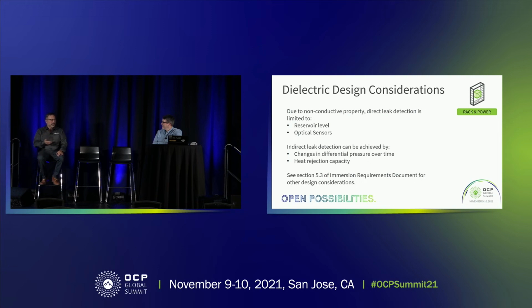Yep. Some of those ancillary things that you don't think about that leaks could cause. The first thing you're thinking about is, oh, I'm losing cooling. But you also have to think safety as well, especially with refrigerants, because the refrigerants will displace oxygen. So, depending on the size of that data center, you might have to have oxygen sensors or some kind of refrigerant evacuation system. But we also, in the glossary in the paper, have some great references you should take a look at, like ASHRAE 34 and 15.